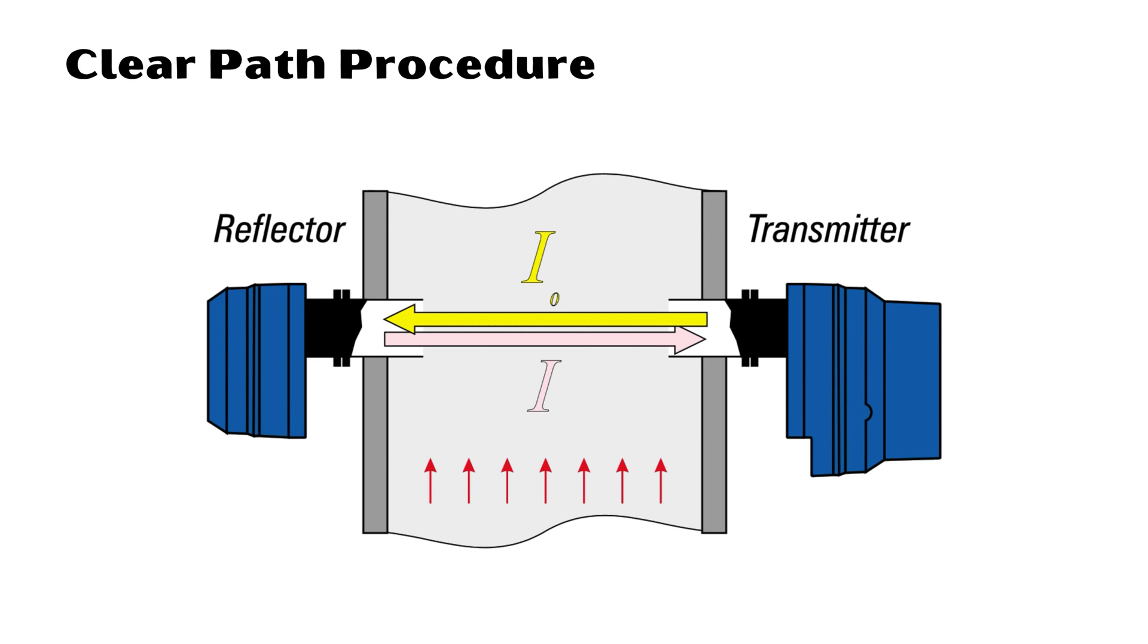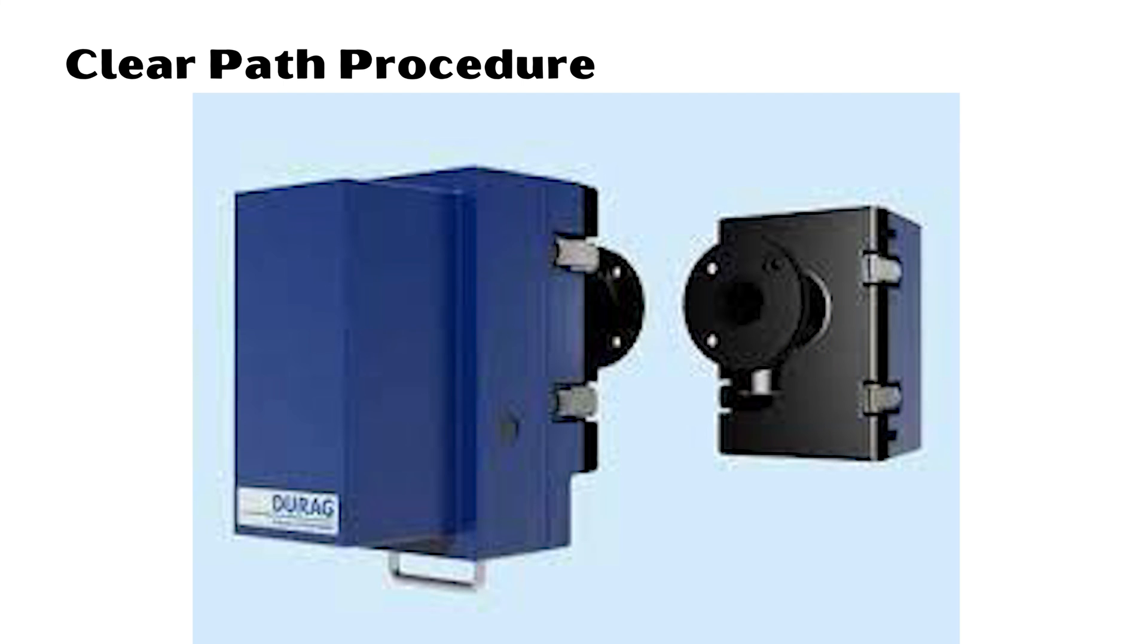Manual internal zero point window check: Normally the window check reading should not need to be electrically adjusted. If the window check reading increases, it indicates there is dust or contamination on the window or zero point reflector. Cleaning these surfaces should return the window check reading to near zero percent opacity. At some time it may be necessary to adjust the window check reading back to zero.